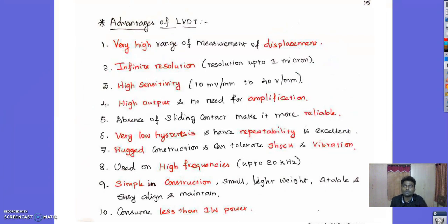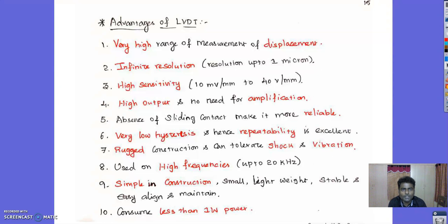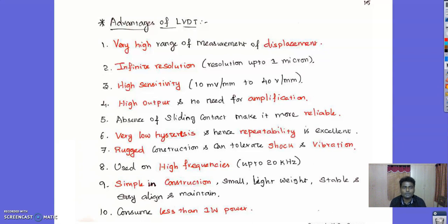The advantages of LVDT include: very high range of displacement measurement with infinite resolution; high sensitivity of 10 mV/mm to 40 V/mm; high output with no need for amplification; absence of sliding contacts makes it more reliable; very low hysteresis resulting in excellent repeatability; rugged construction that can tolerate shocks and vibrations; operation at high frequencies up to 20 kHz; simple and lightweight construction; easy to align and maintain; and it consumes less than one watt of power.